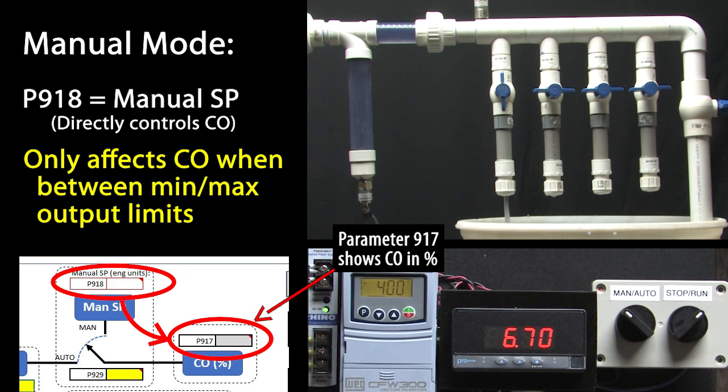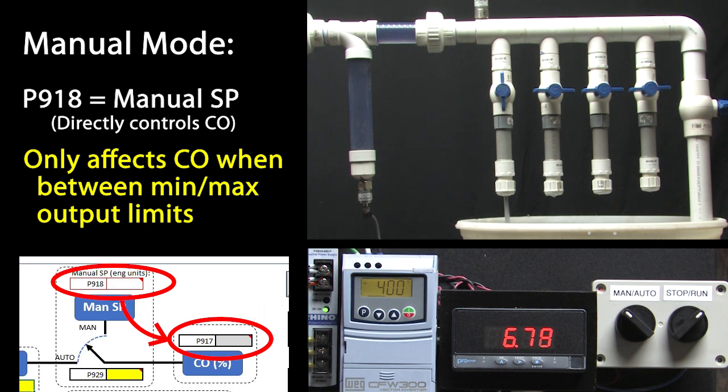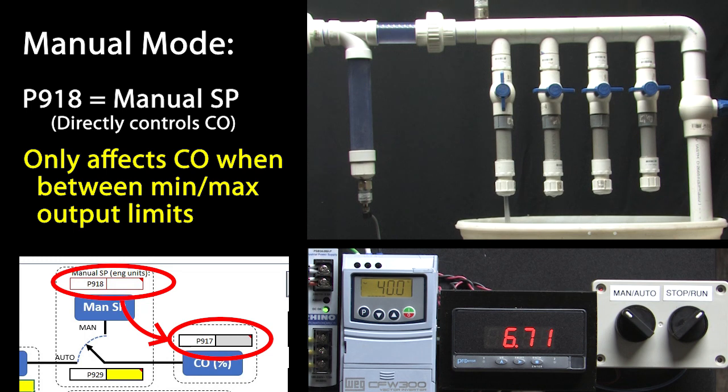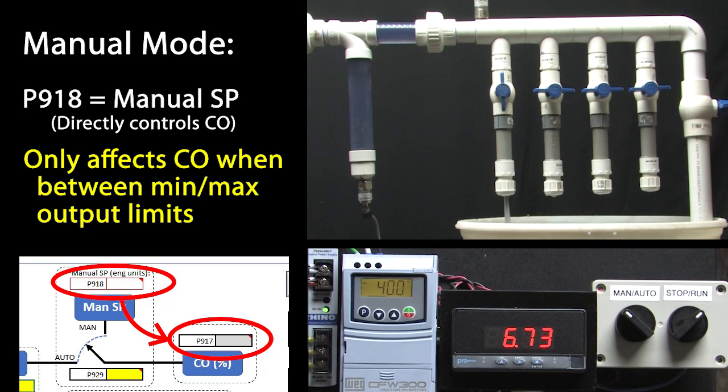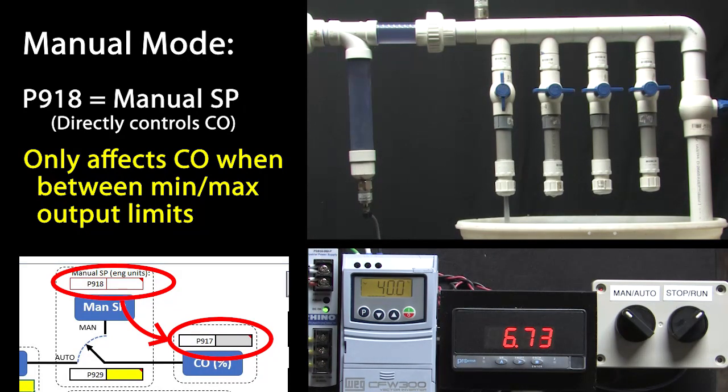Could we have set up PID first and then generated our curves using this manual mode where we manually control the output of the drive? Yep, just widen up the min and max drive frequencies before you start and change them to the values you need before running PID. Great, manual mode works.